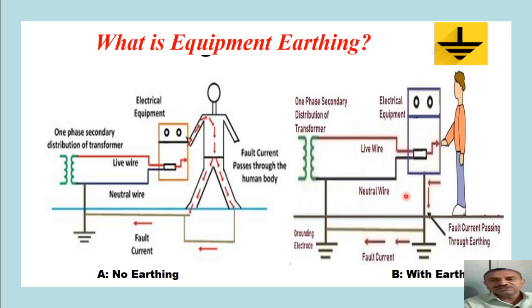By using earthing, as shown in this right side diagram. Here again the same electrical equipment is there, but now you can observe that the body of the electrical equipment is connected to the earth wire and earth electrode which we described earlier. It means that whatever fault has taken place in the electrical equipment, which has resulted in making the body of the equipment charged, that is at live wire voltage, now, as the body is directly in contact with the earth, the potential of the body will always be maintained at zero potential. So the current will get the path of least resistance through the earthing system, and that current can be detected and we can even save the electrical equipment also.